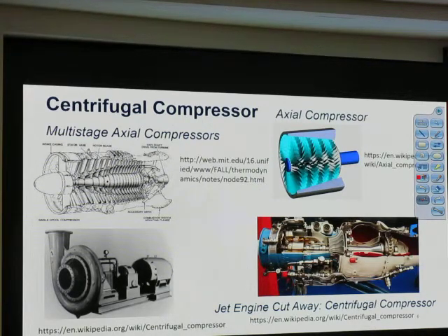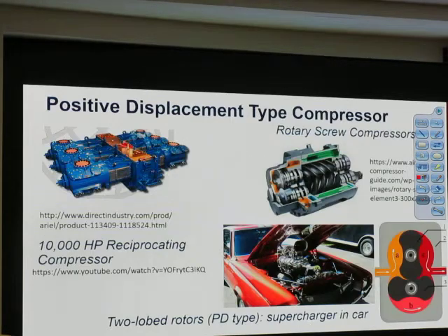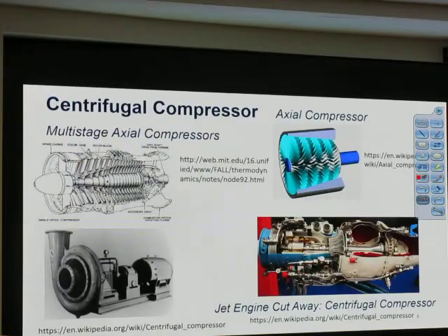Yeah. So those turbine pumps, or turbine compressors as you hear them referred to, are used to move very high volume. We used them in the Middle East on offshore platforms. These were 12,500 horsepower units, moving about 125 million cubic feet a day through each compressor. Then we had two trains of those compressing gas to gas lift. We have 250 million a day total gas lift on two of those.